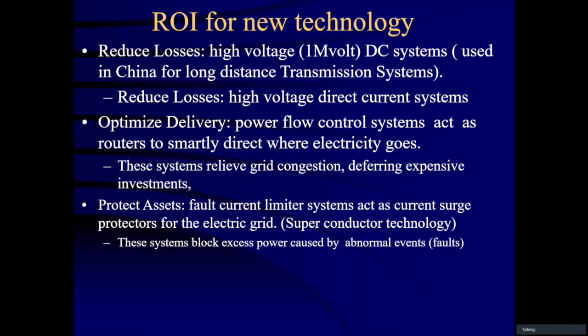Protect assets. So one of the issues is when there's a major fault, particularly at transmission, it has the opportunity to create tremendous damage if they cannot clear the fault quickly enough. And now there are superconductor technologies being used today that act as current limiters for surges. I believe the cost of those will decline and they will become more prevalent, particularly in transmission where that is a major cost factor.